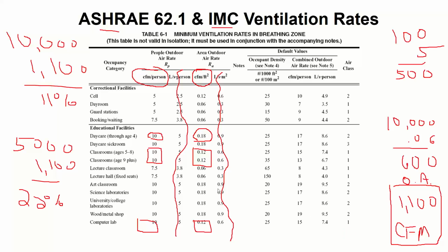Will asks, lots of commercial buildings and schools have no outside air ventilation unless the windows are open, please comment. Older buildings, and sometimes new ones, often have what's called natural ventilation. I work for an HVAC distributor, a mechanical company, so I'm totally opposed to natural ventilation. Just because it has the word natural doesn't mean it's good, it's not like natural foods. Natural ventilation means the building accidentally brings air in, versus mechanical ventilation where I force it in and measure it. So natural ventilation means I don't have an outside air intake on my air handler.